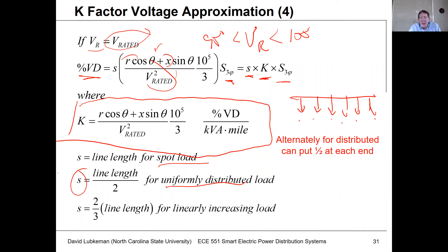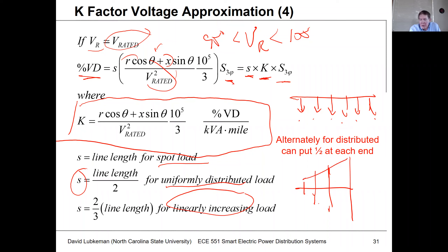There's another case — if we have a linearly increasing load, like the substation planning example showing a triangular-shaped service area, then the effective line length is going to be two-thirds times the actual line length.